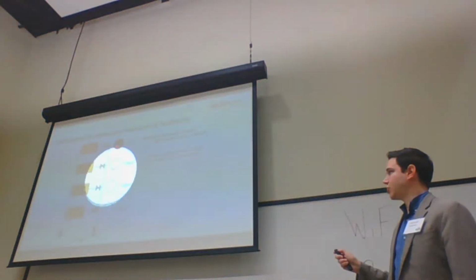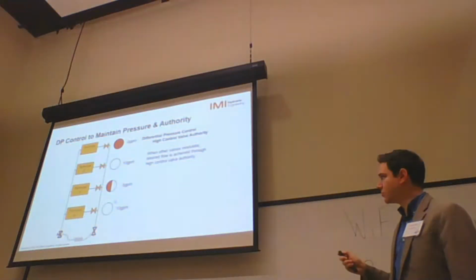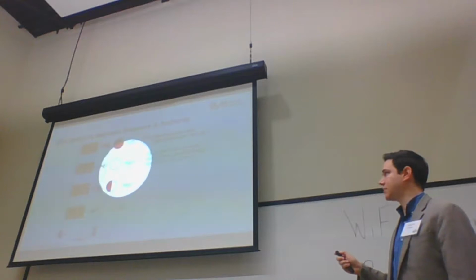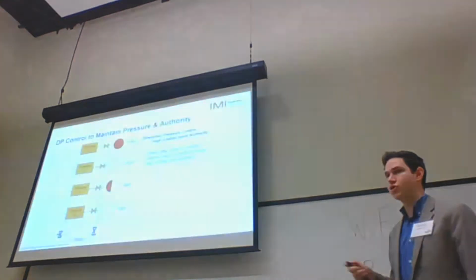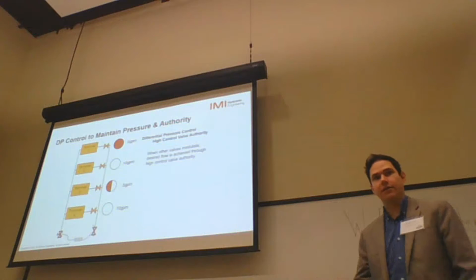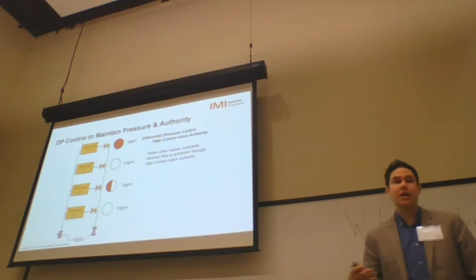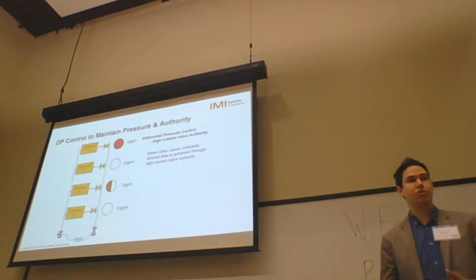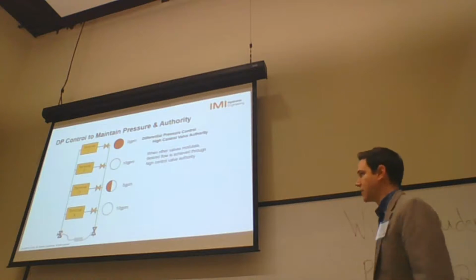If I'm closing one valve in the end, I'm not changing the flow for the other 3 that are still open. Closing terminal 3 by 50%, still keeping the same flow rate for the other 2 that are still open. And again, this is a way to get a pressure independent model, a pressure independent branch for my installation.